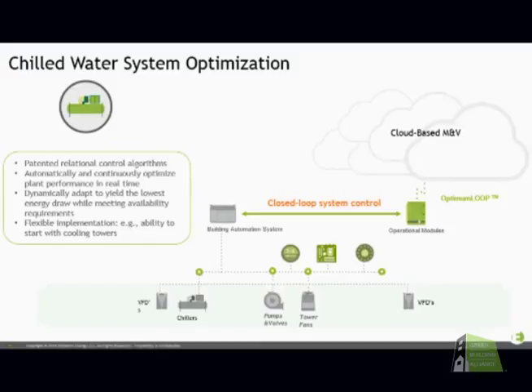So this is looking at the entire system, and it's making adjustments. And going back to the 3 laws that Matt was talking about before, really the only way to do this effectively is to constantly adjust to changes in the system. So throughout a given day, you're always going to have changes in terms of outdoor air temperature, of course, and that'll affect your cooling towers, how efficiently they're able to reject heat.